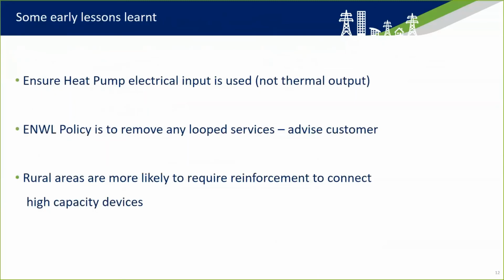So, coming towards the end, we've been connecting these devices for really a couple of years now, and there are some common things we've observed. It's quite common, when there's an application for a heat pump, for the installer to put on the form the thermal output rather than the electrical input to the device. It's quite important because generally the thermal output is going to be of an order of 2 or 3 times greater than the electrical input, and that could make the connection difficult. So it's important to check you've put the electrical input on.